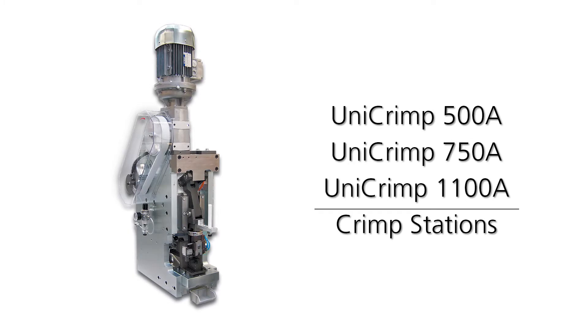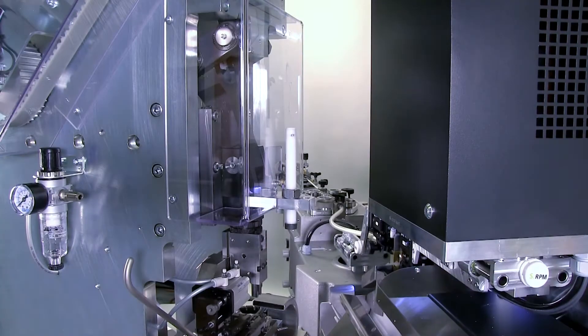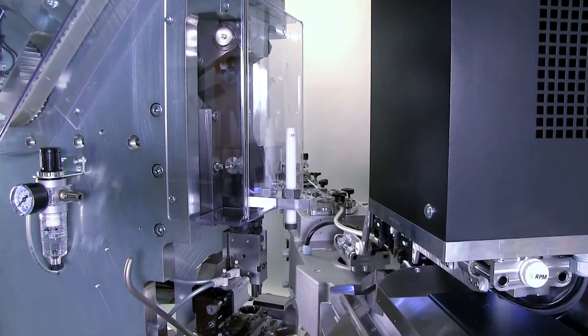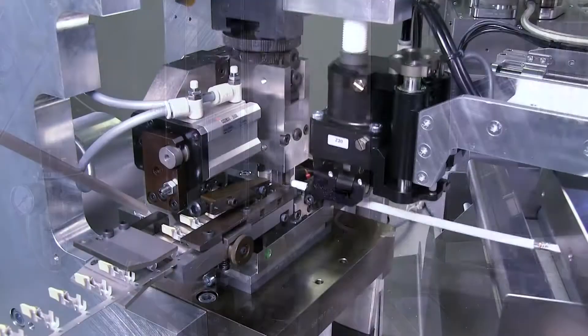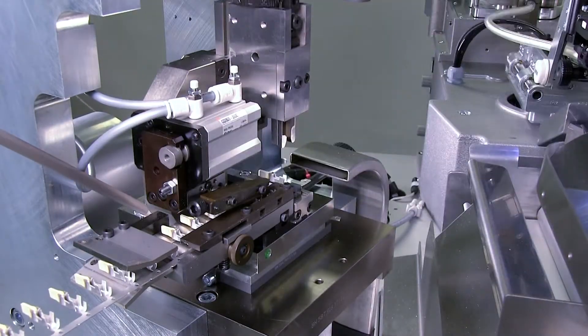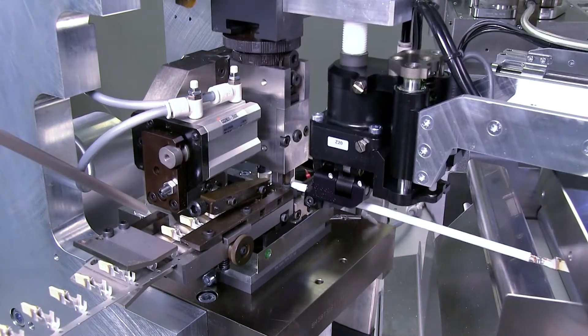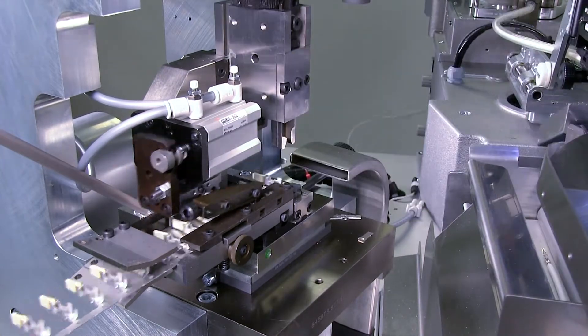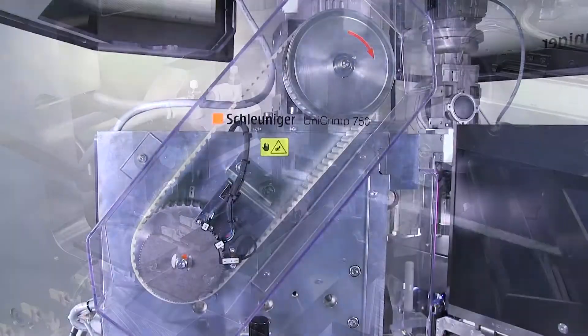For heavy-duty crimping applications, the Unicrimp 500, 750 and 1100 crimping stations are available for use with the Crimp Center 67HD16 and HD25. With 5, 7.5 and 11 tons of crimping force respectively, these Unicrimp stations process wire cross-sections up to 25 mm² or 4 gauge with the proper crimp applicator.